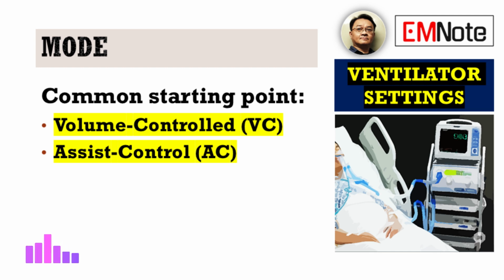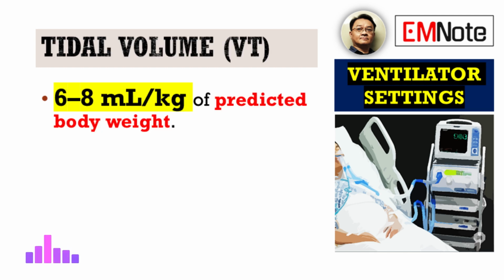Okay, volume or assist control. Now, let's get into the specific initial parameters that define those breaths. What about the tidal volume? How precisely do we calculate that for a patient? Right, tidal volume. That's the volume of air delivered with each breath. It should be set between 6 to 8 milliliters per kilogram of the patient's predicted body weight. And that's a critical point. It's predicted body weight, not their actual body weight.